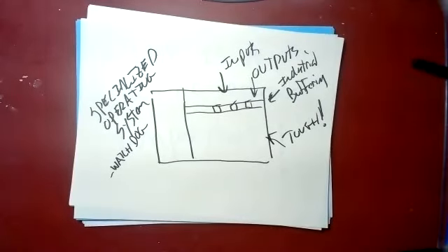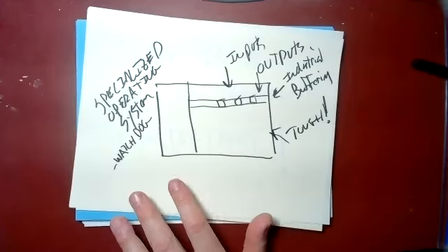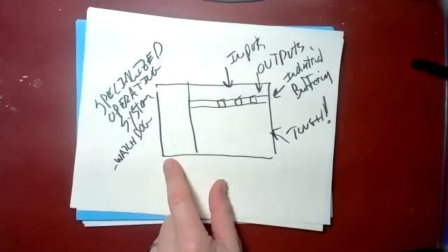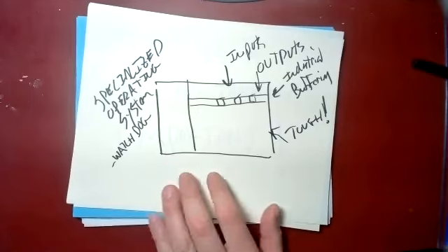It's a special little software component that just checks up on the operating system running properly. And if the operating system is running too slowly, unlike your Microsoft Windows PC, if it starts slowing down, ain't nobody going to notice but you, and you start cursing at it. But a PLC has its own software built in called the watchdog, and that watchdog will start barking if it slows down and will cause special actions to occur, to reboot it, to warn the operators, to do some other things, whatever you program it to do.